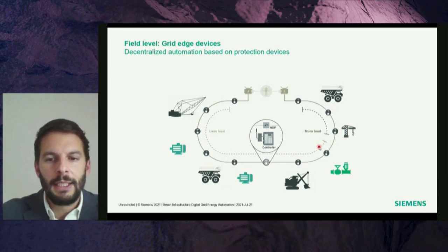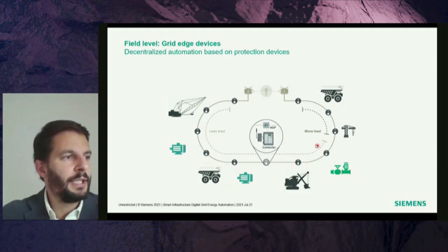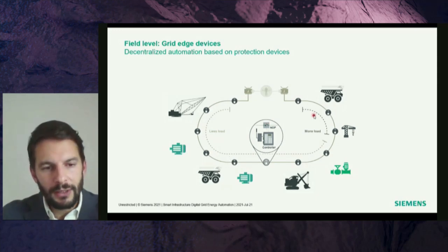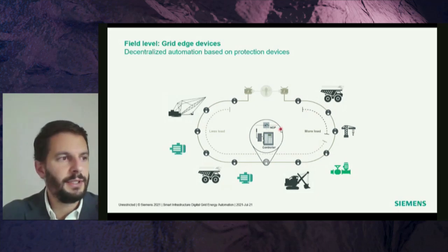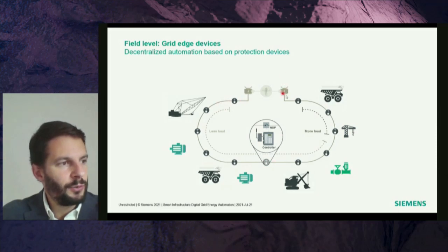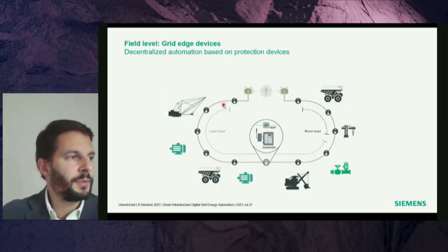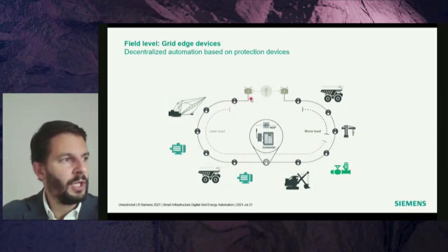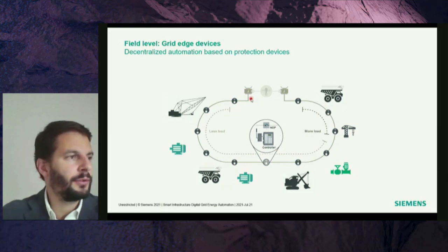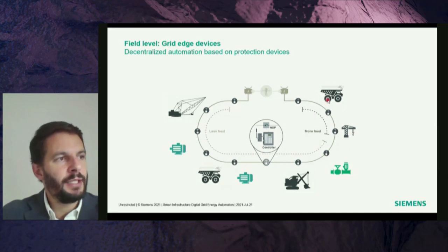At the end of the day, based on the intelligent grid edge devices installed along the loop, we have the possibility to detect in real time the load profile of the nodes along the loop structure. From the example, station or in-feed A supplies loads down to the normally open point, and in-feed B supplies from the other side. Currently the field devices tell us there's less load on the left side, maybe less machinery operating at that point of the day, and we're running some kind of overload in this particular part of the loop section.